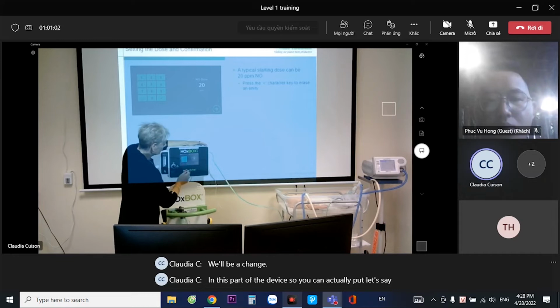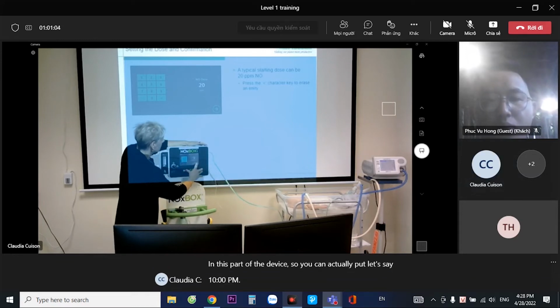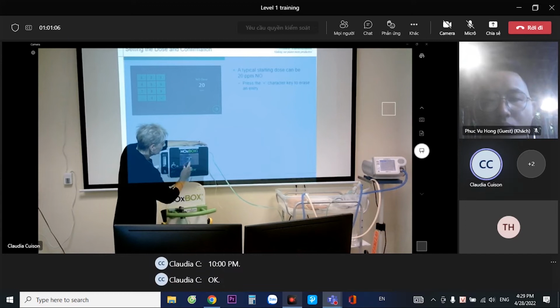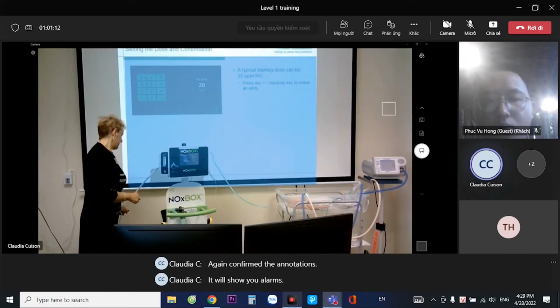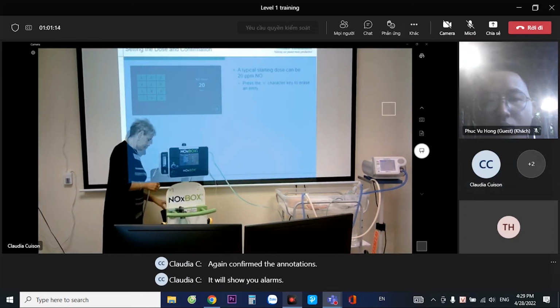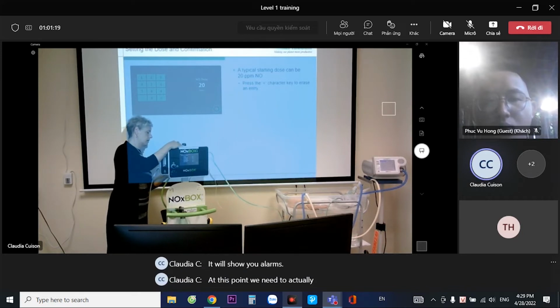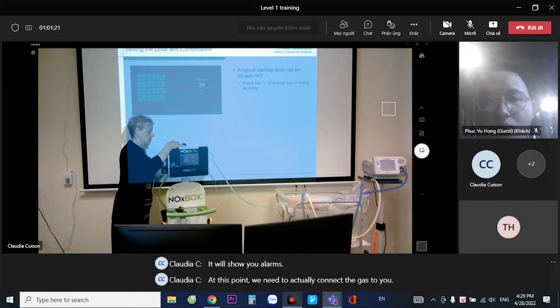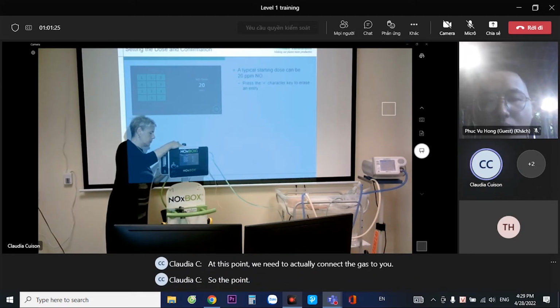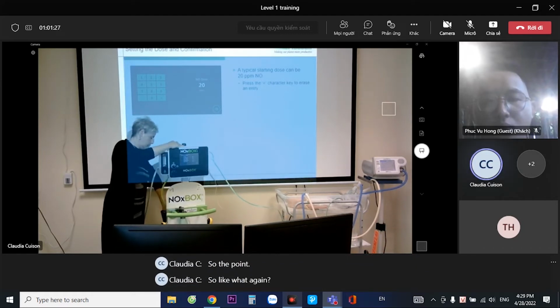So you can actually put, let's say, 10 ppm. Okay. Again, confirm the NO dose. It will show you alarms. At this point, we need to actually connect the gas to the correct port again. Open the valve.